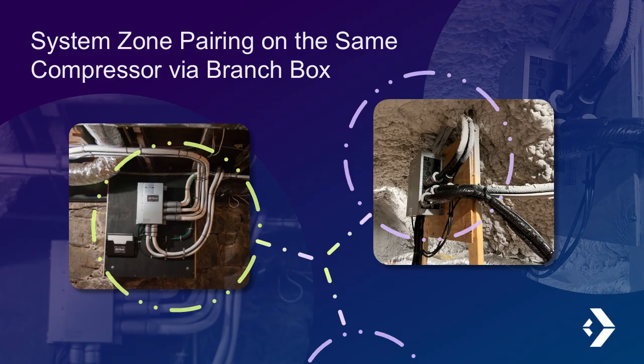Branch boxes are a key component in a multi-zone system. They distribute refrigerant from a single outdoor unit to multiple indoor units. Inside the branch box are valves that open and close to control the flow of refrigerant, ensuring each indoor unit receives the precise amount needed for heating or cooling based on demand. This design gives the homeowner more control over their comfort, tailored to their specific needs. Additionally, it can help reduce energy waste.